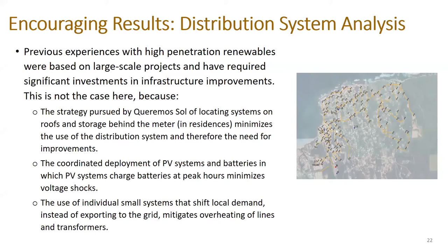Therefore, it's inherently less taxing on the distribution system. There are peak periods where there's a lot of solar activity and not so much load, where there is a little bit of power moving on the distribution system and the upgrades are necessary to accommodate that. But that's, again, a much smaller problem than we anticipated. And that's largely because of the combination of the PV systems with the battery systems.